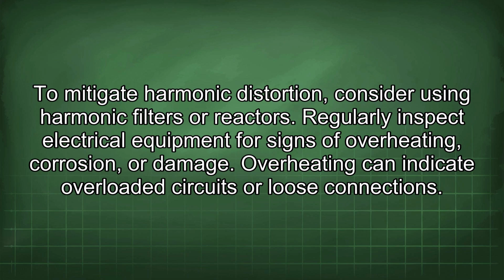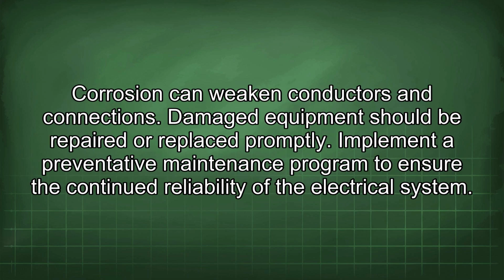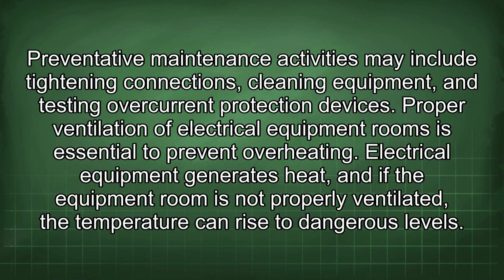Regularly inspect electrical equipment for signs of overheating, corrosion, or damage. Overheating can indicate overloaded circuits or loose connections. Corrosion can weaken conductors and connections. Damaged equipment should be repaired or replaced promptly. Implement a preventative maintenance program to ensure the continued reliability of the electrical system. Preventative maintenance activities may include tightening connections, cleaning equipment, and testing overcurrent protection devices.